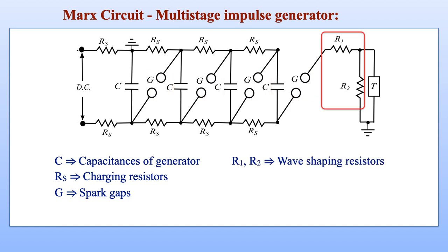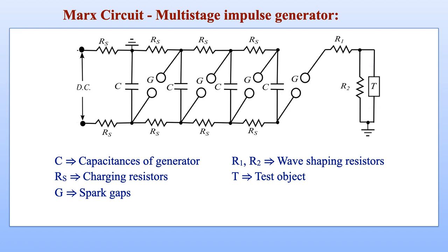Apart from this, there are resistances known as wave shaping resistors R1 and R2 connected across the output of the multi-stage impulse generator, and lastly the test object or the sample insulation which will be tested with the high voltage impulse. Initially the spark gaps, represented by capital G, have their spacing adjusted to a large value such that they will not conduct at the charging voltage of the capacitors connected across them.